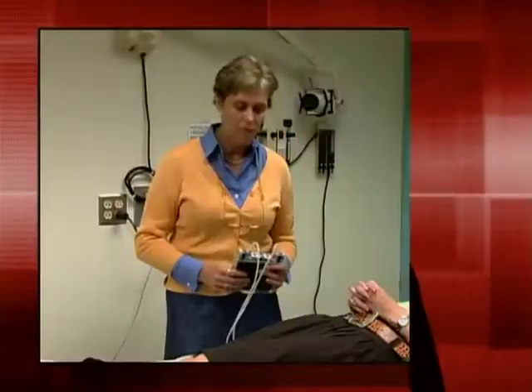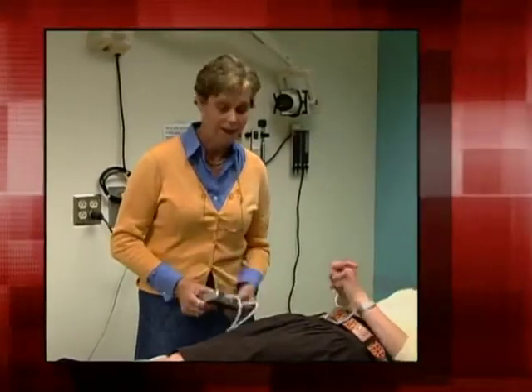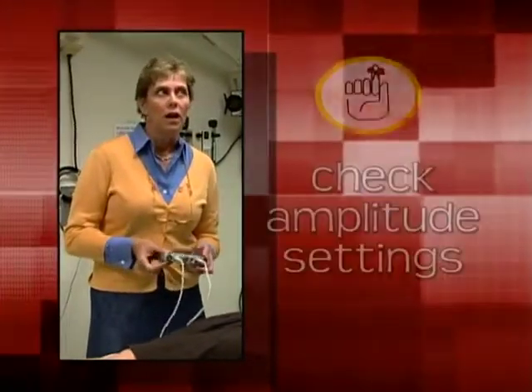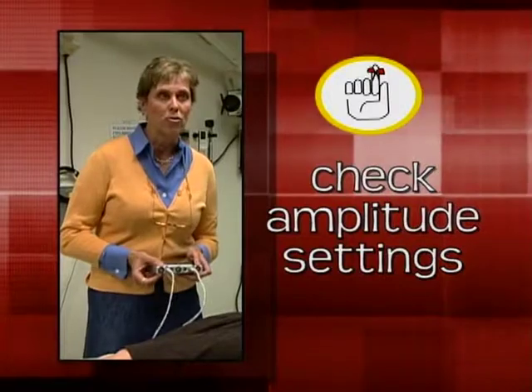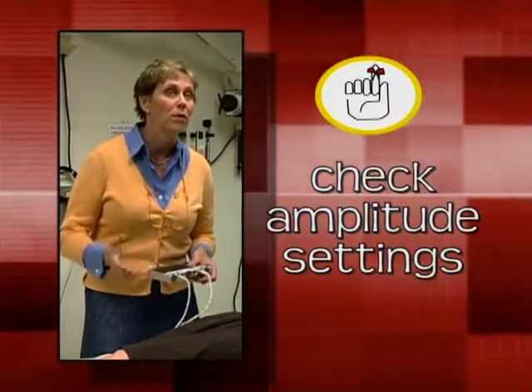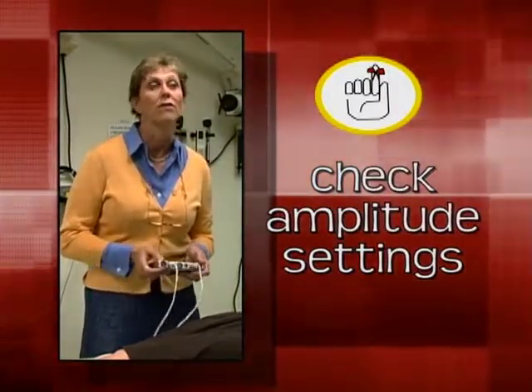What do you do when the pacers aren't working as they should? Melinda's methodical approach is to first check the transmitter. The first thing you would look for is simple stuff. Did the amplitude dials get reset? Did they get bumped? Did they get turned down? Those are the kind of things that are an easy fix.